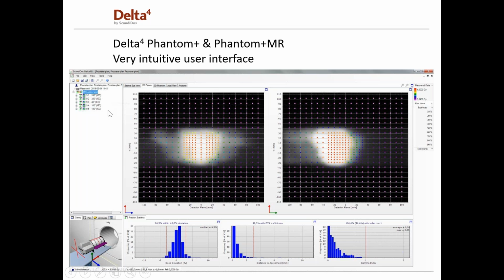Over on this side, you have the complete plan that we've selected here. So the analysis that's done down here with dose deviation, distance to agreement, and gamma index is all based upon doing the complete plan. However, I can select the individual beams and do an analysis on the individual beam or arc. So the software is very fast, very easy to use, and very intuitive.